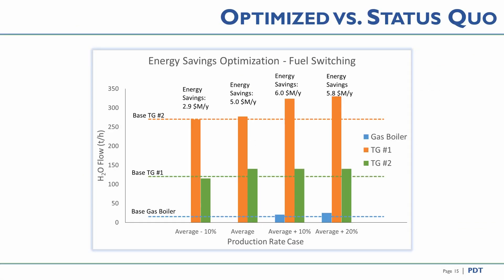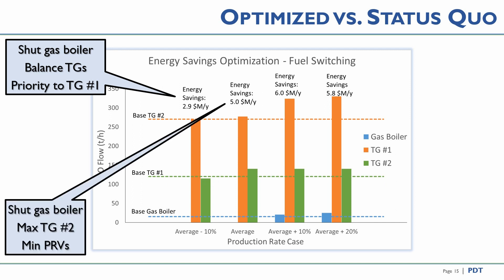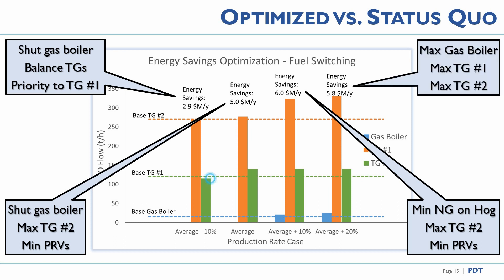This important slide shows the complexity of the problem and the energy savings that can be gained with four different production rates. The horizontal dashed lines indicate where the power systems can operate successfully without changes as production changes, but money is left on the table. Each different production rate has a different optimal solution. At low production rate we should shut the gas boiler and give priority to the condensing turbine. At average production rate — similar to the case I just demonstrated — we minimize natural gas on the hog boiler, maximize turbo generator 2, and minimize pressure reducing valves. At higher production rates we maximize the gas boiler and put more through the PRVs while maximizing the turbo generator.